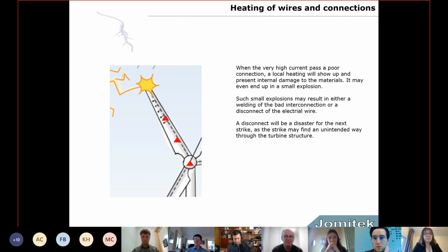If we have poor connections along the down conductor, we can see heating of the down conductor material and the interconnections. If some interconnections are not properly attached, there will be an ignition - it functions as a spark gap, and at that ignition we'll see a small explosion. This is okay if we are in free air, but if it's within fiber material, it's a bad situation.